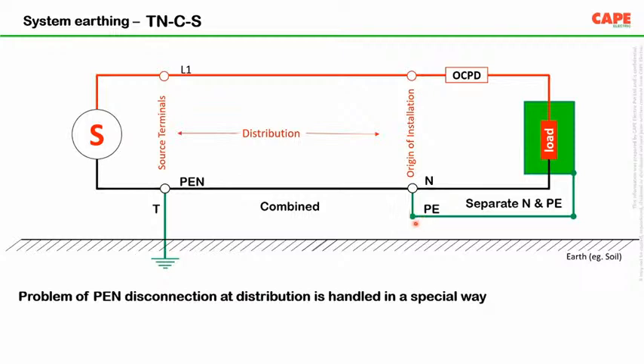Why is this called the earthed terminal? Because this terminal is earthed through the conductor, through the PEN conductor, and finally, this is earth. This is the earth of the circuit, the place where the neutral is connected to the earth. Earthed terminal means the exposed conductive part of the building, there is a provision for the fault current to return back to the earth, and this is the earthed terminal. It has actually nothing to do with the pit in soil. Yes.